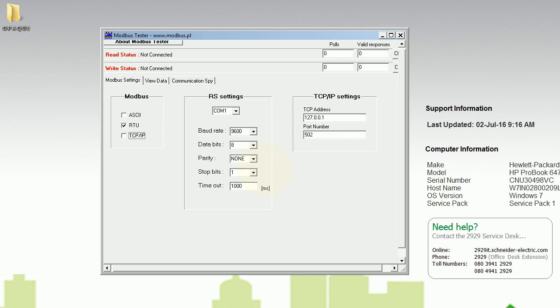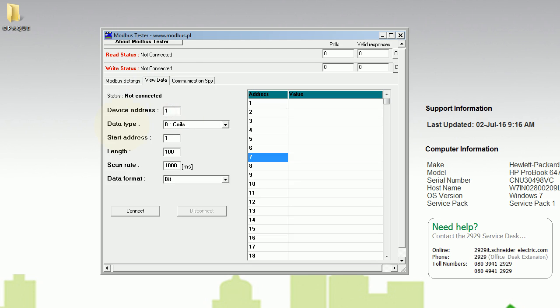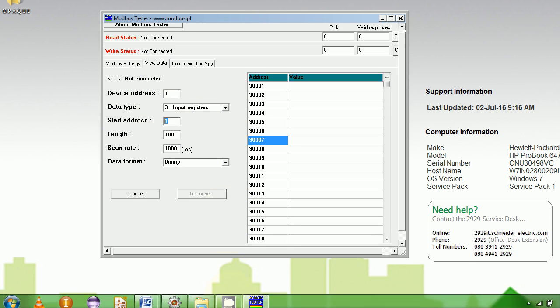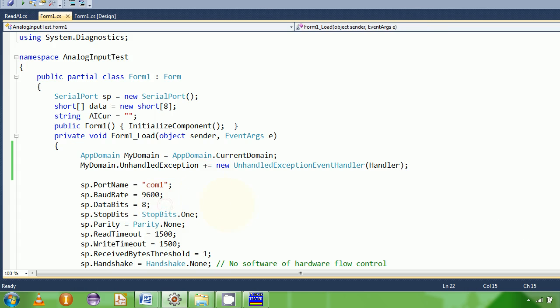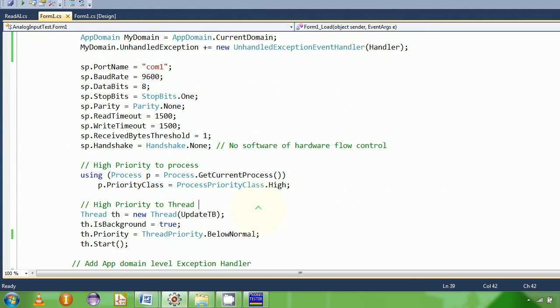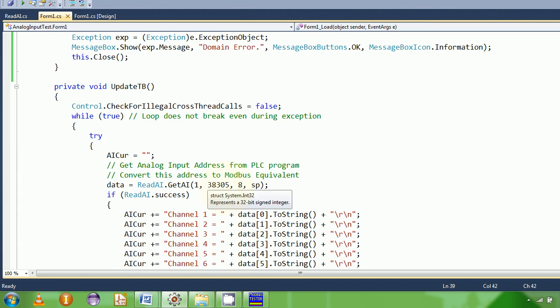These are the serial port settings, and the device address is the address of the PLC. Normally the PLC would be set to one if it's not on an RS-485 network; if it is on a network, you want to set it to the actual value on the PLC. Currently we'll be reading analog input, and the starting address has to be set from here. Since it's a read analog input, the function code three is already known to the driver.